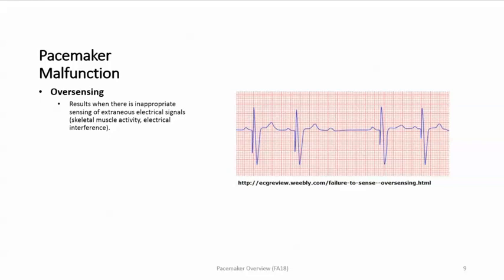You can also have over sensing. This results when there is inappropriate sensing of extraneous electrical signals, such as skeletal muscle activity or electrical interference. These signals are interpreted by the pacemaker as intrinsic activity, and as a result the pacemaker does not fire. So it fired appropriately at first, but then picked up interference and mistook it for intrinsic electrical activity, causing it to withhold pacing — that is over sensing.